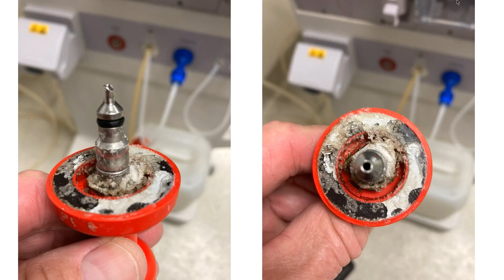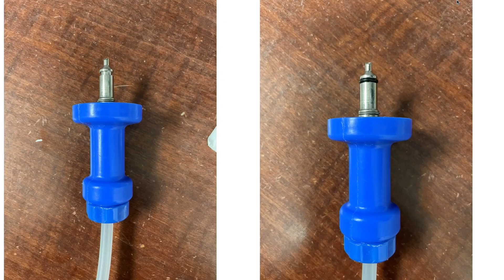Ain't that pretty? That too should be part of the wipe down in your disinfection, because even tiny specks of concentrate on your O-rings can literally change your conductivity. And air, even the tiniest amount of air into your concentrate line, will change your conductivity. And that's the same thing with bicarbonate. And a lot of times what happens is these O-rings are not being wiped down and get crusted, and the salt acts like sandpaper, so those get torn. And if they get torn or a little nick, guess what happens to the conductivity? It goes down.